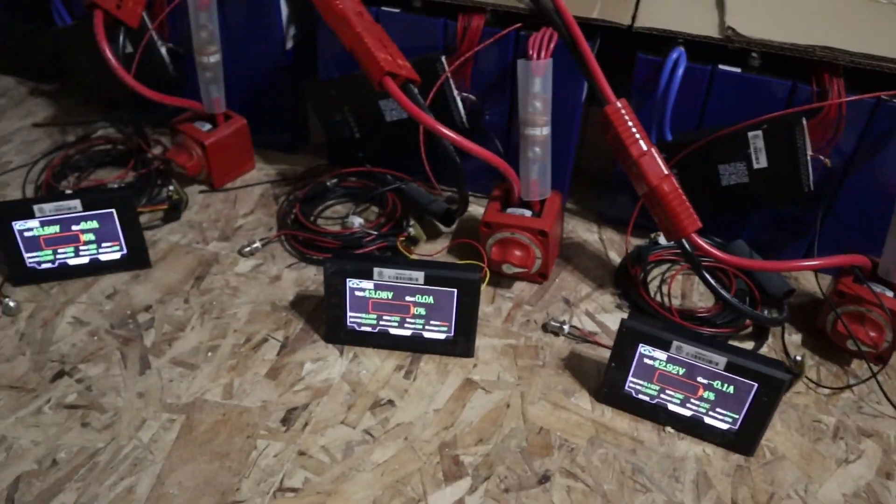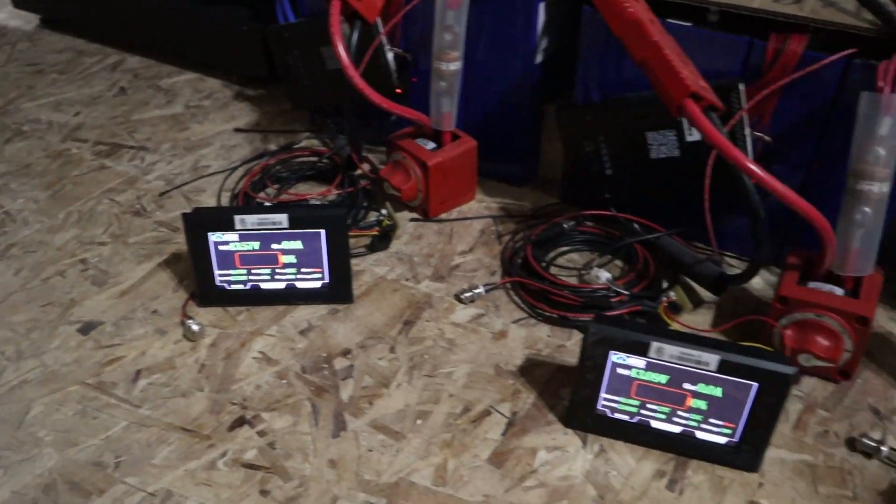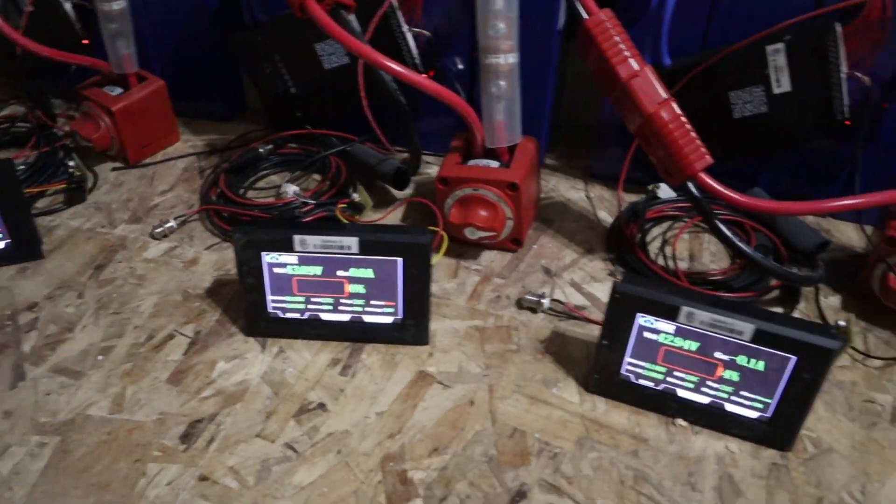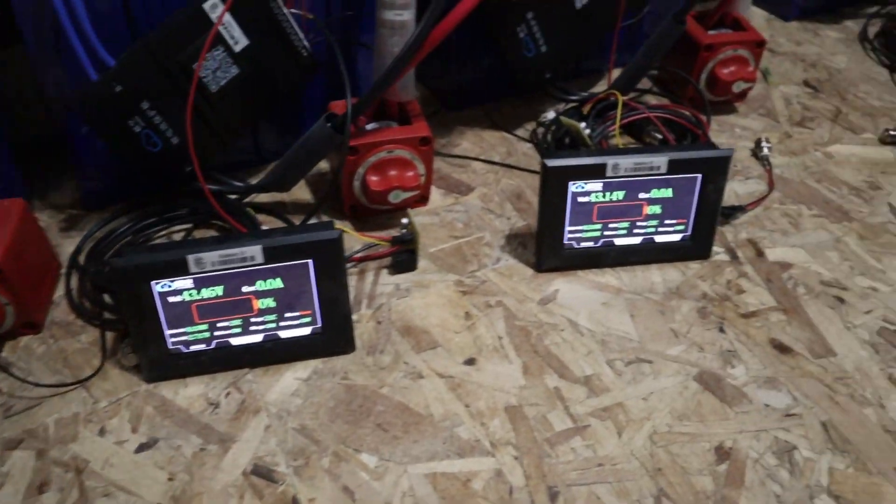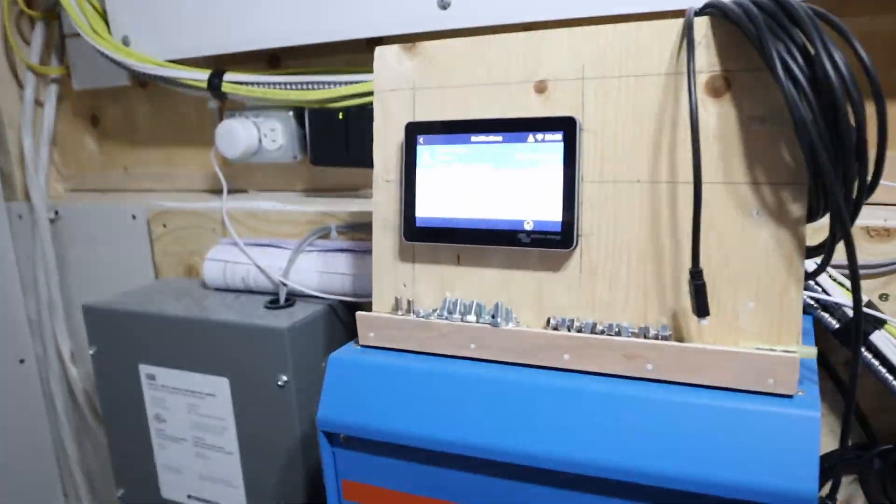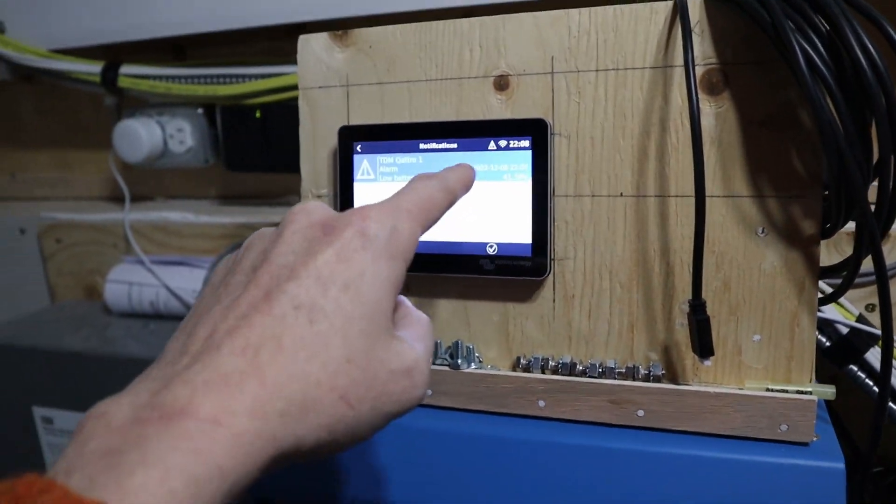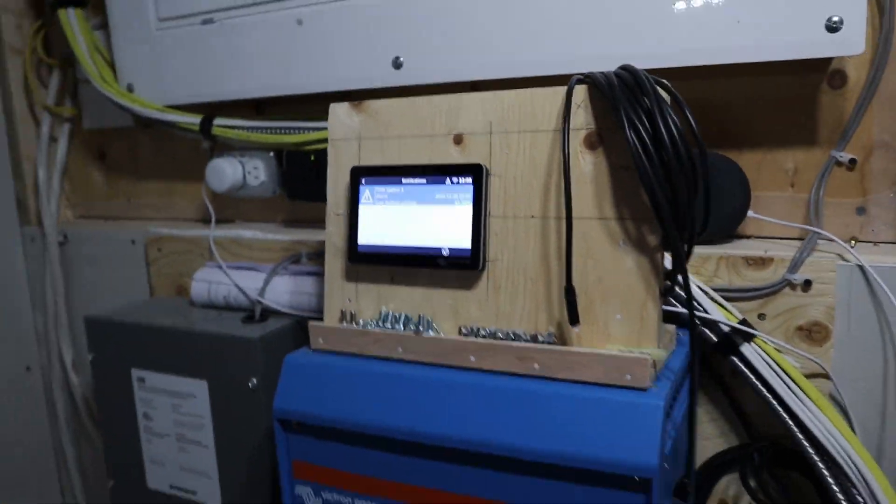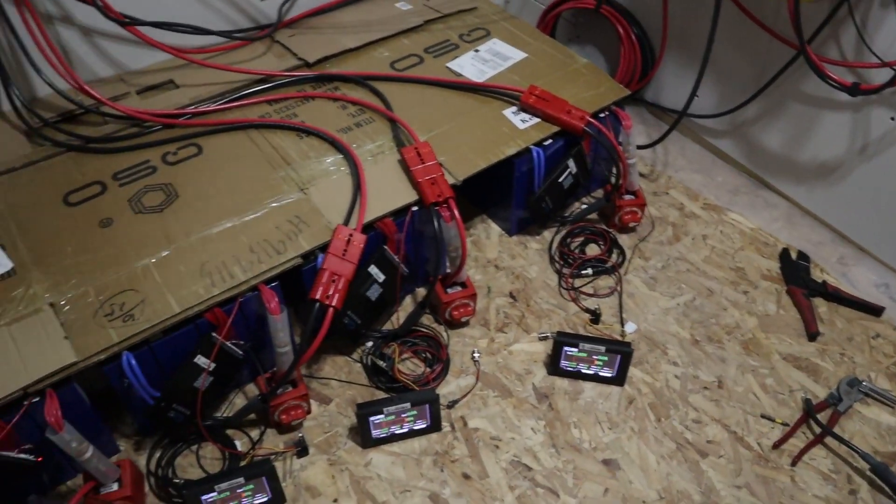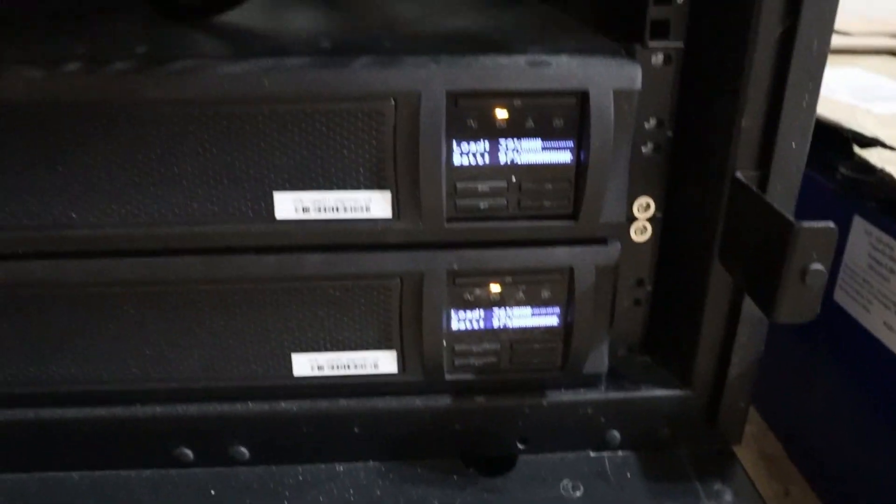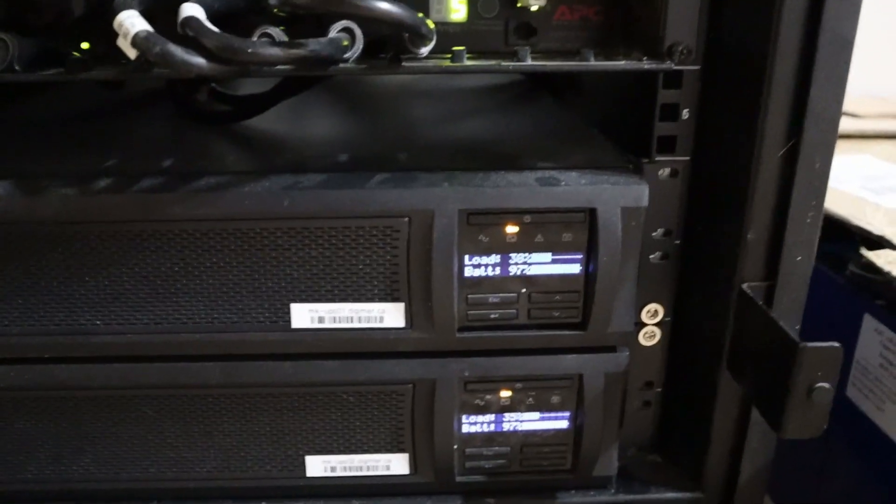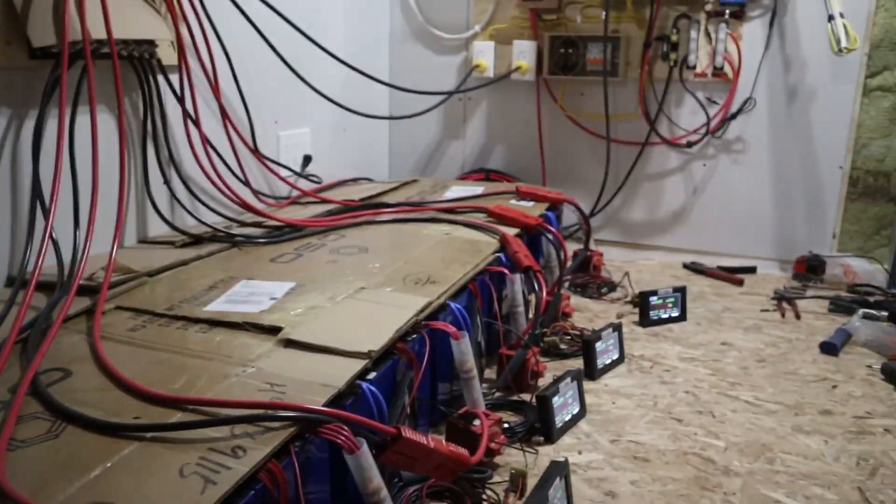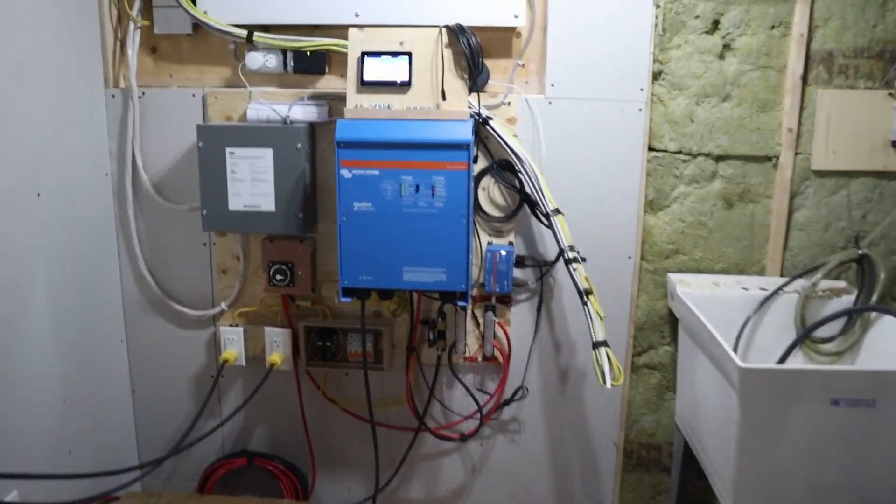Okay it was showing four percent left and then it all went to zero. So it guessed a bit wrong. Yeah this is completely disconnected. In fact I don't even know how it's still running because all of the outputs are off. The normal UPSs are now running on their own internal batteries. I just missed the shutdown.